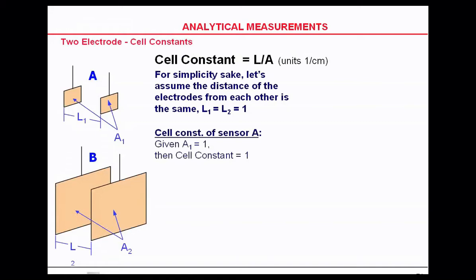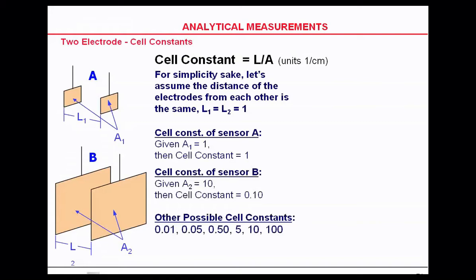You'd use different cell constants for different measurements. A 0.01 might be used for 0 to 2 microsiemens. A 0.1 might be used for 0 to 200 microsiemens. A cell constant of 10 for each plate and the distance between them would give you a cell constant of not 10 but 0.10.